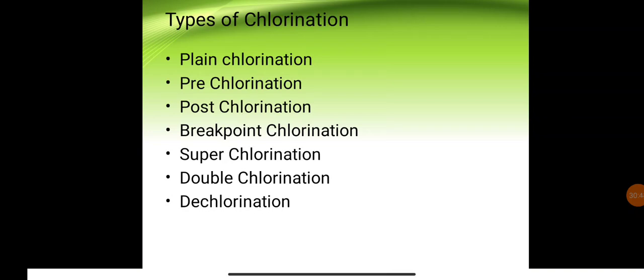And what is meant by breakpoint chlorination? It is the point beyond which any further addition of chlorine will appear equally as free chlorine. So point C is called the breakpoint. Beyond that point, any further addition of chlorine will appear equally as free chlorine.